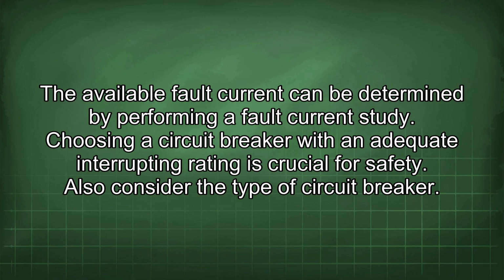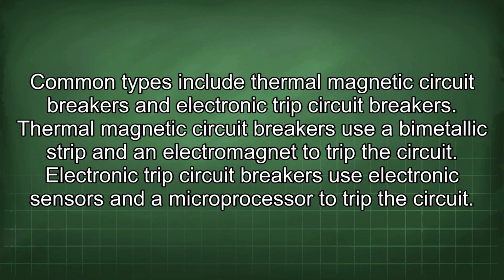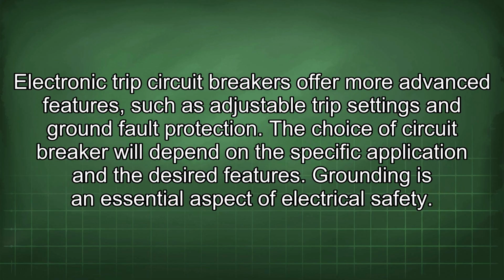Also consider the type of circuit breaker. Common types include thermal magnetic circuit breakers and electronic trip circuit breakers. Thermal magnetic circuit breakers use a bimetallic strip and an electromagnet to trip the circuit. Electronic tripped circuit breakers use electronic sensors and a microprocessor to trip the circuit. Electronic tripped circuit breakers offer more advanced features, such as adjustable trip settings and ground fault protection. The choice of circuit breaker will depend on the specific application and the desired features.